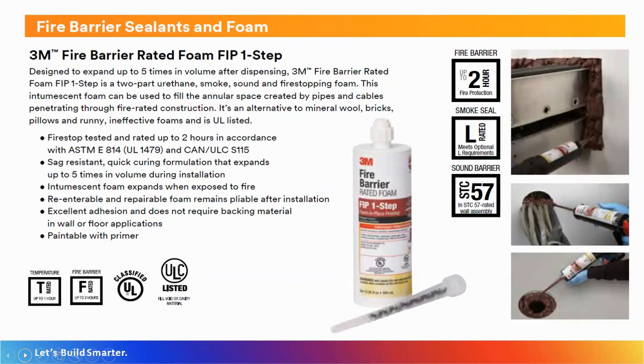The next product I'm going to show you is the fire barrier foam, or the FIP One Step. This is a relatively newer product to the firestop offering. It's a 2-component urethane foam that can be used as a smoke, sound, and of course a fire stopping foam. Once this material is dispensed, it expands up to 5 times in volume. That eliminates the need for mineral wool backing behind your fire stopping installation.